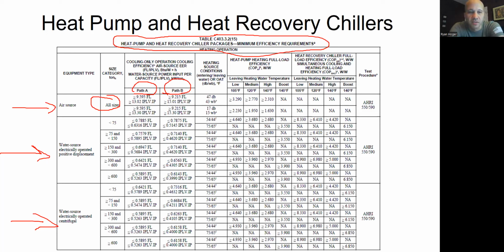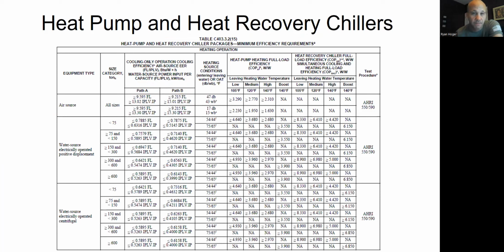So you get these two ways to comply, one of which is harder to meet the full load requirement. The other one's harder to meet the part load requirement. So these are the efficiencies that you have to meet on the cooling side of the equation, right? And these are very similar to what everybody does when they design a chiller plant now. And then you have the heating efficiencies over on the right. Let me clear some of my slop off just for argument's sake.